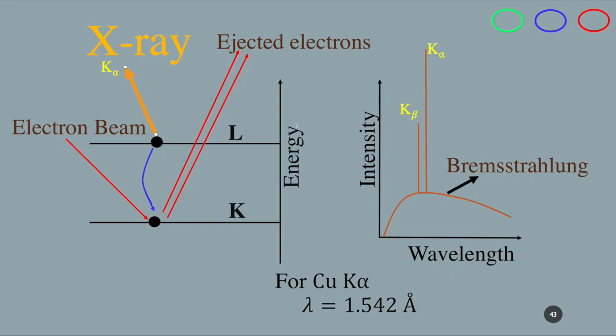Because all K lines arise from a loss of electrons in the K shell, K alpha and K beta lines always appear at the same time. If you plot the spectrum of wavelength and intensity, we get something like this.